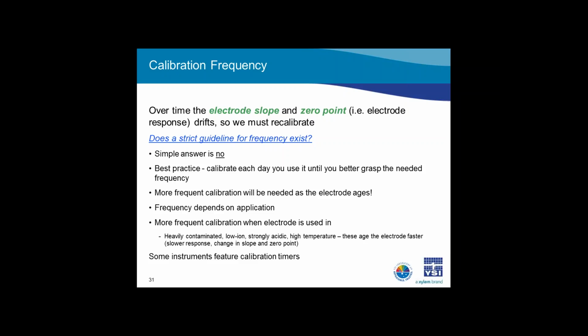More frequent calibrations will also be required when the application requires it. This could be due to applications that may cause the sensor to drift faster, such as samples that are heavily contaminated, have low ionic strength, are strongly acidic, or when the electrodes are used in higher temperature samples. Additionally, some applications may require a higher accuracy or precision than others. In that case, the sensor should also be calibrated frequently.